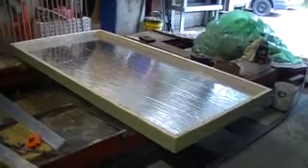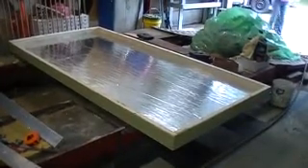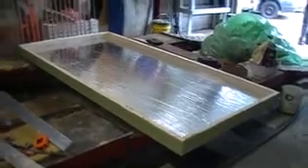I just kind of put together my own idea of how I want to set it up. In my case, I put the insulation inside the box — I saw some people put it on the outside. As you can see, there are my riser pipes with my header at the top; the footer is in behind and currently all sealed. The gauge is actually backwards, but I have 30 pounds of air pressure in it right now, just double-checking for leaks. That is on the upper end of what copper would normally stand.